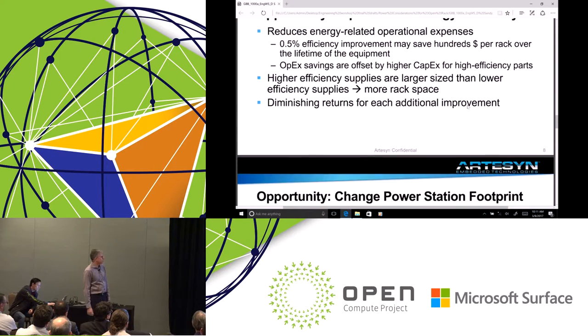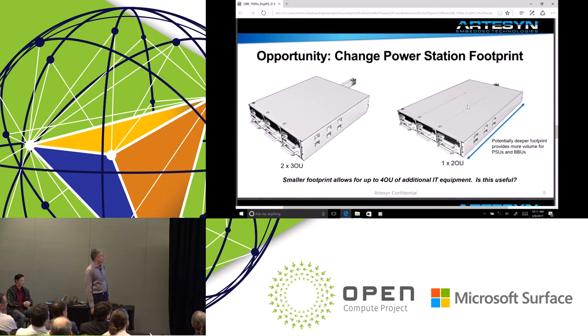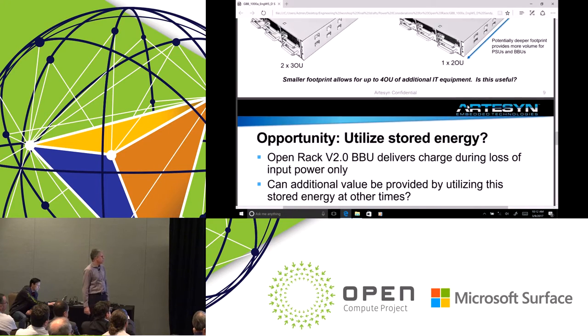Next slide. Along with power density, we want to probably use as much rack space as we possibly can for this. By making a larger power station, you can reduce your volumetric density of power, and then push up your efficiency along with your capacity within the power shelf. But there are other trade-offs - for this particular shelf, the depth was chosen so that there's enough cable bend radius for the shelf. So again, more trade-offs.